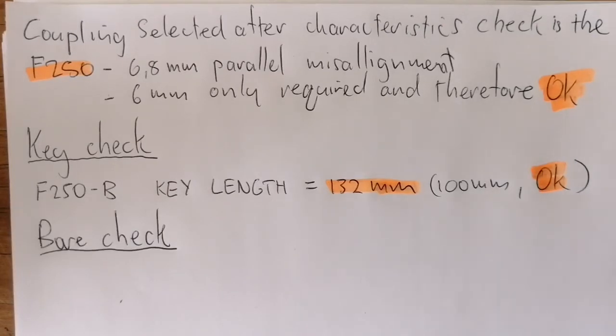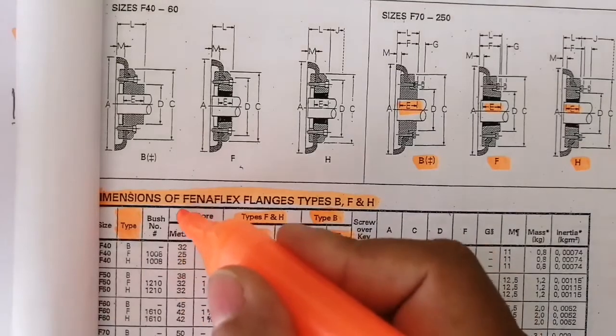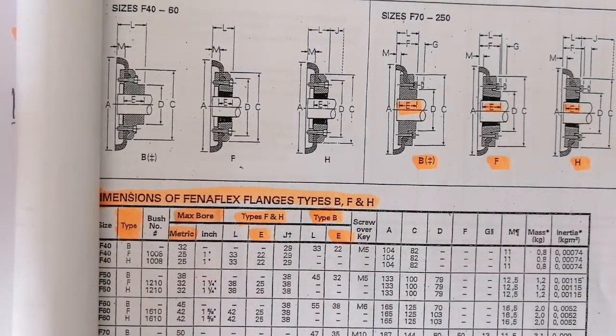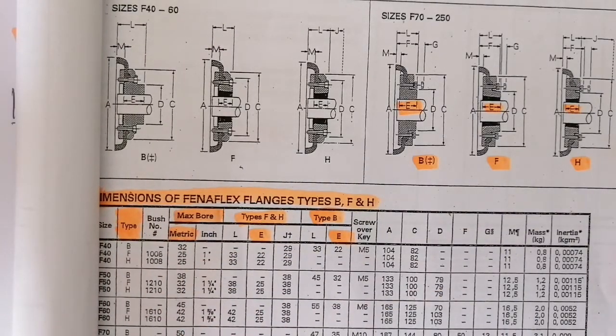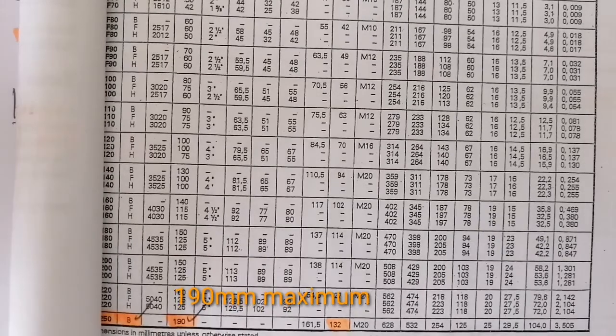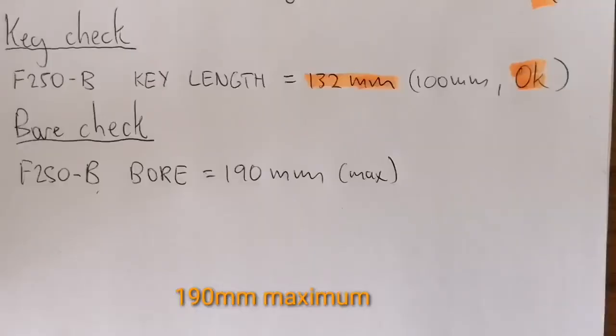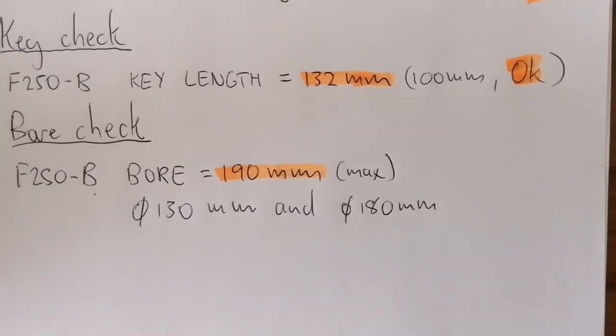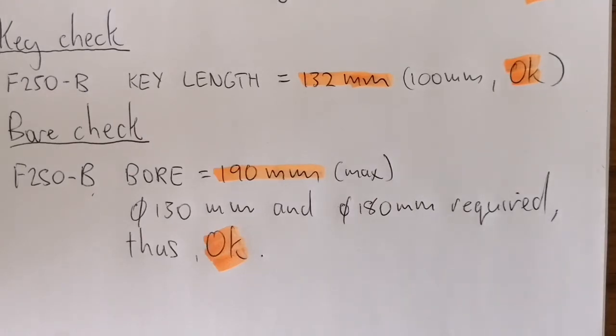Bore check - the bore check is featured on top of the table. We'll be working with metric bore sizes. Going downwards to the F250, we have a maximum bore of 190 millimeters. We can see that the F250 type B bore equals 190 millimeters max. Our shaft sizes are 130 millimeters and 180 millimeters required. Thus it is okay because 190 is greater than 130 and 180 respectively.